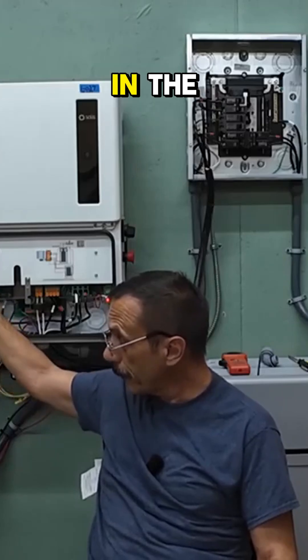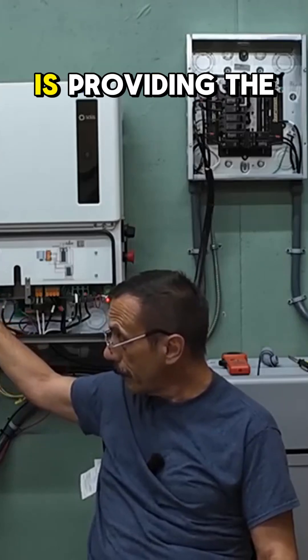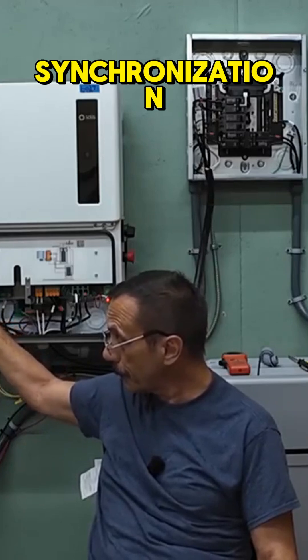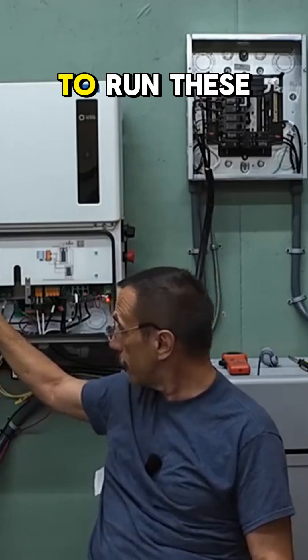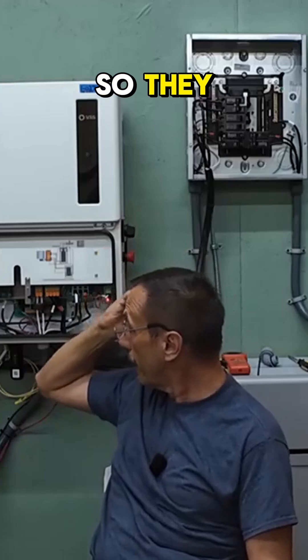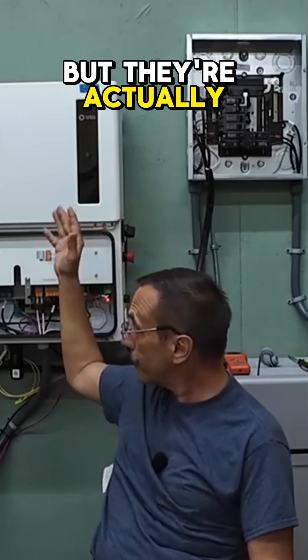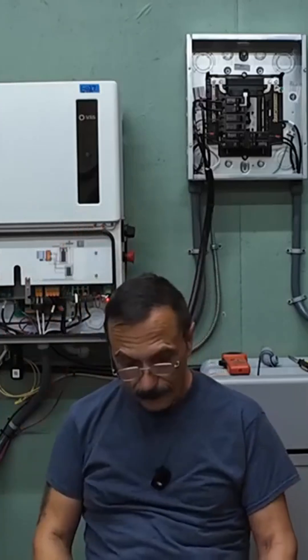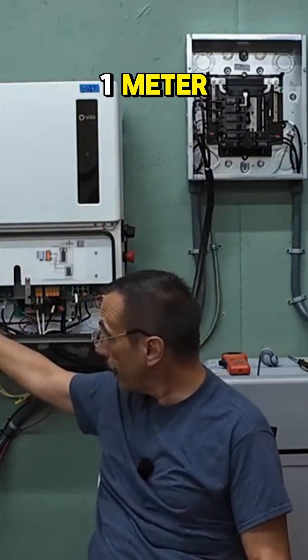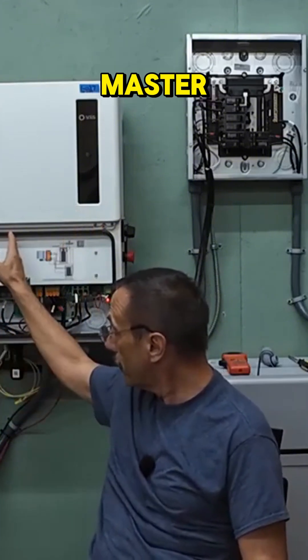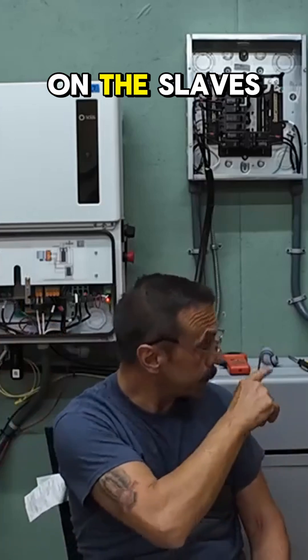My main inverter in the solar shed is providing the 60 hertz synchronization to run these two inverters. They think they're on grid, but they're actually off grid. So you only need one meter connected to the master. You don't put a meter on the slaves.